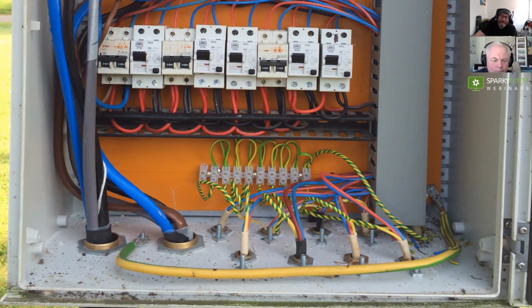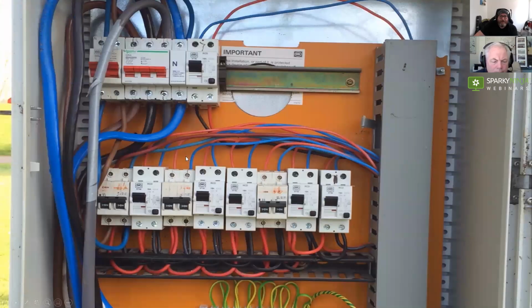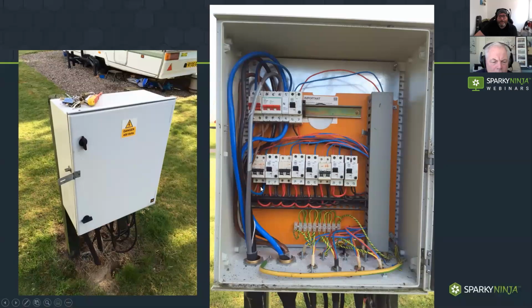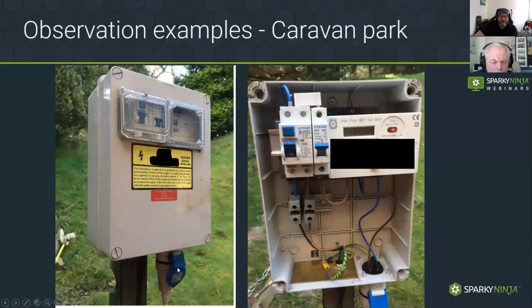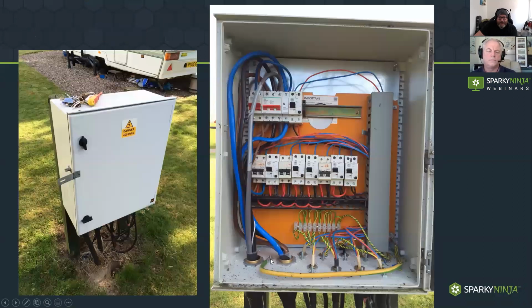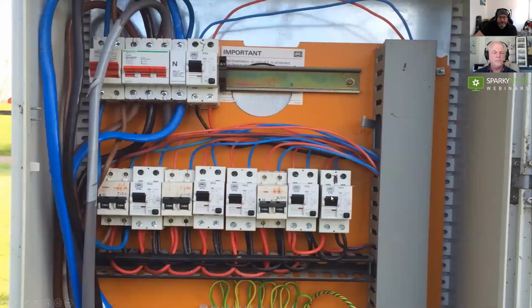So it's all locked up, but the main question really here is, do we have the right protection amounts? Now in here, go back to the single. So the caravan connected to this has overcurrents, has residual current protection. So that's fine, technically, for everything plugged into that. But the cable feeding that, they also need necessary overcurrent protection, which these ones coming off of these RCDs, they do not.